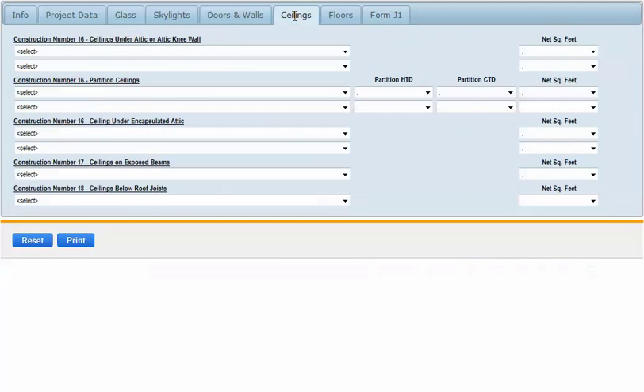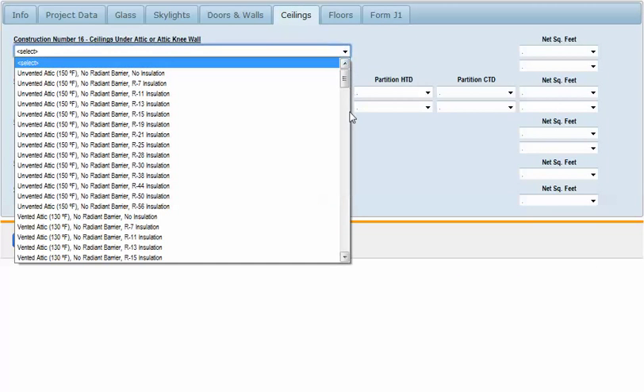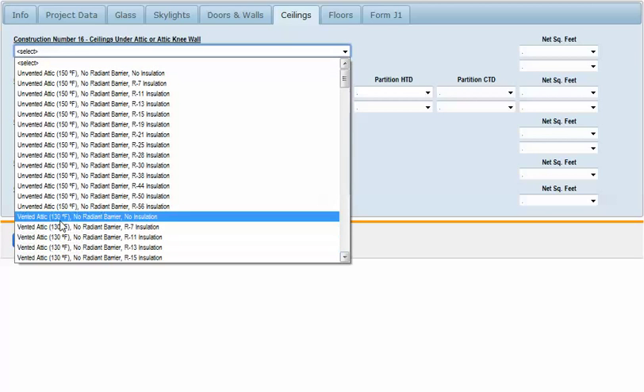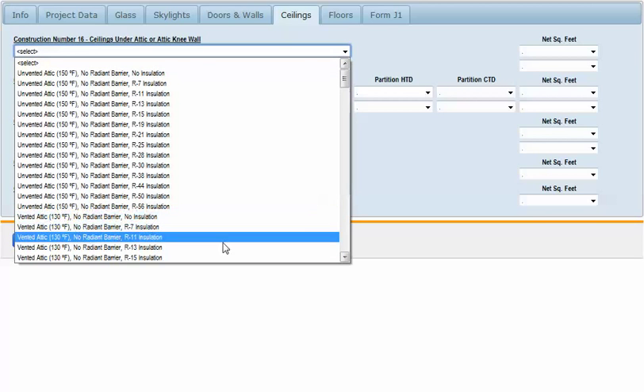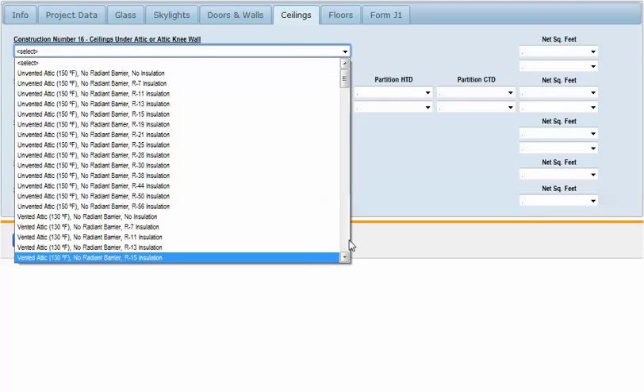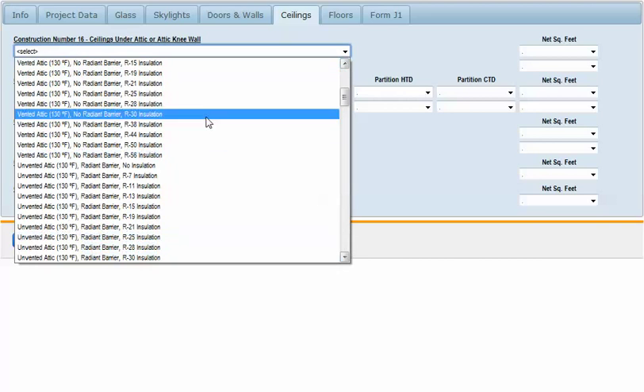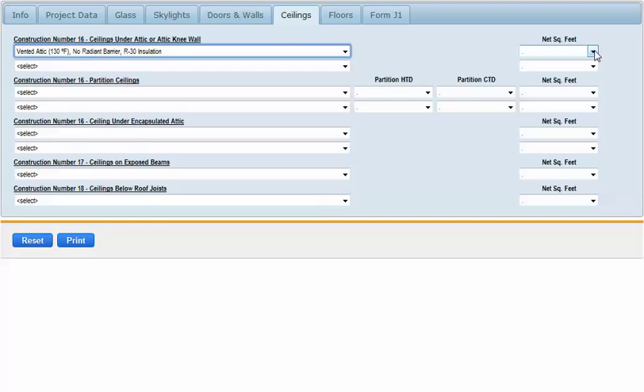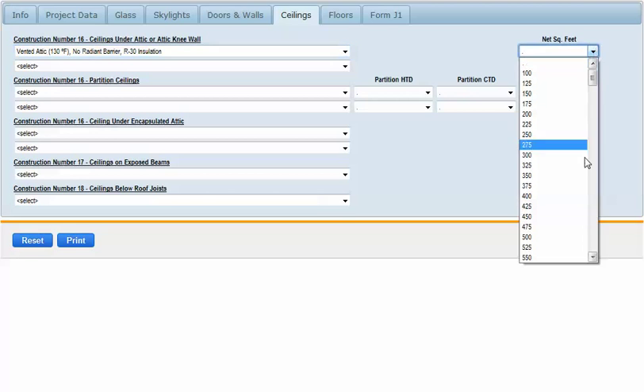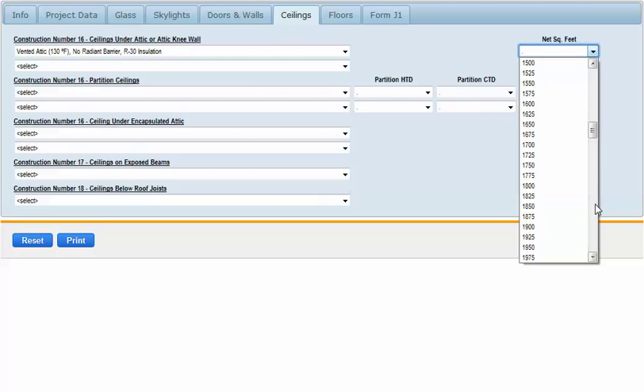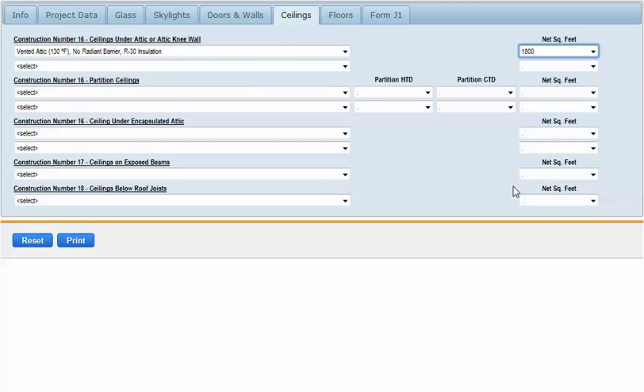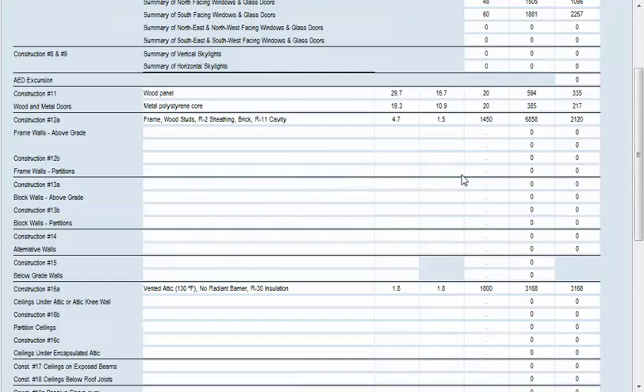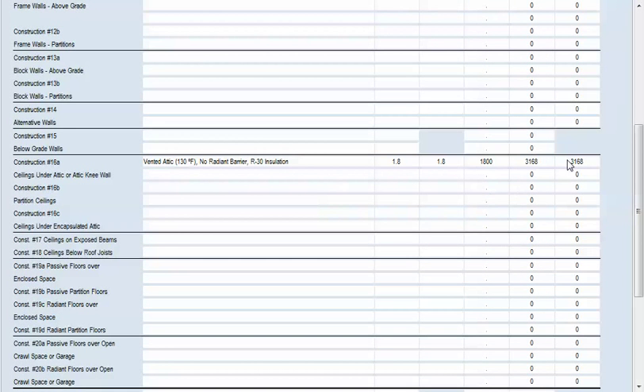Next we'll go to our ceilings. Remember we chose a 130 degree attic for our ductwork. This particular example is going to have R30 insulation, no radiant barrier. For net square feet you would deduct any skylights out of the ceiling. We had that 1800 square foot house so we'd have 1800 square feet of ceiling area. Looking back at our J1 form we'll see that's been transferred over.